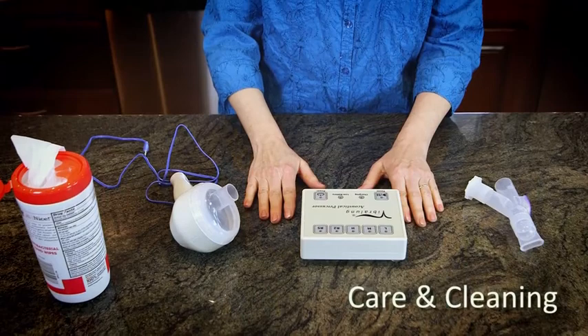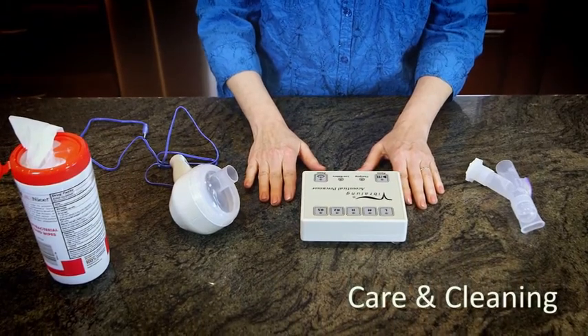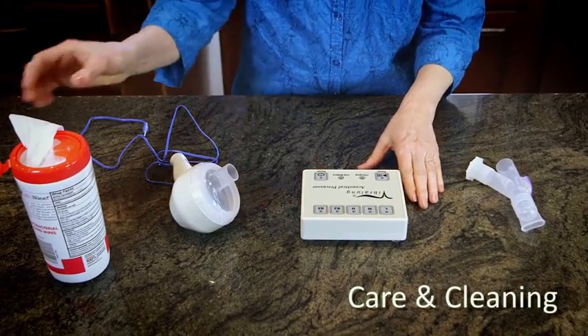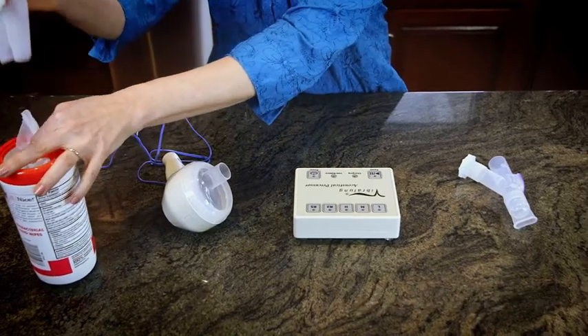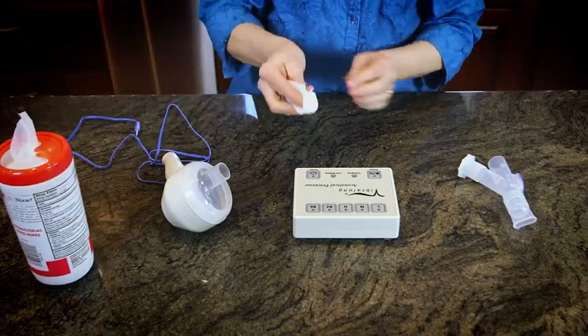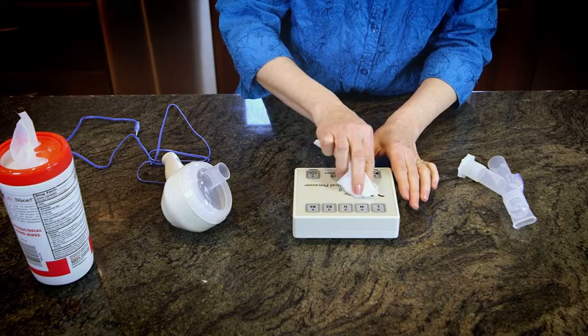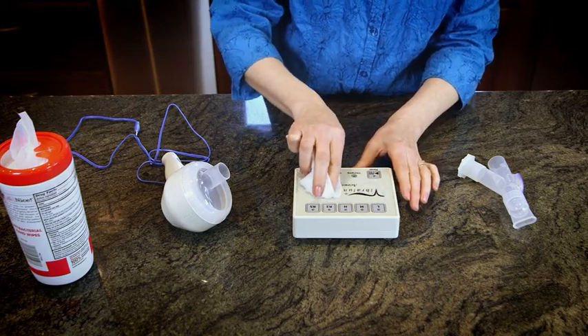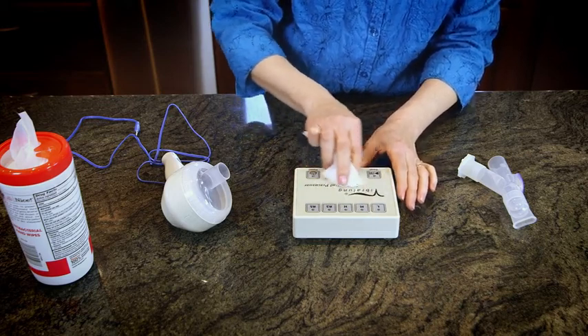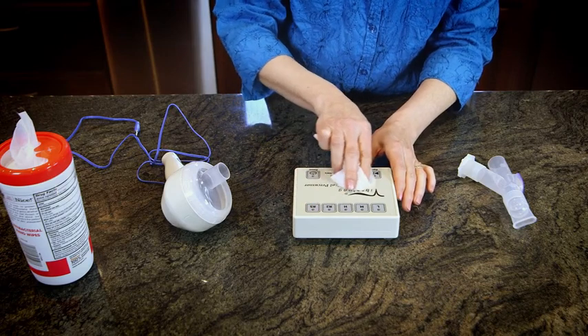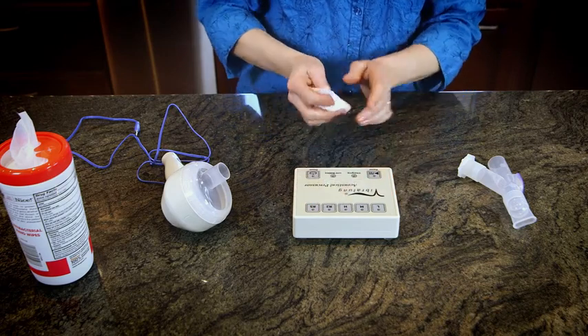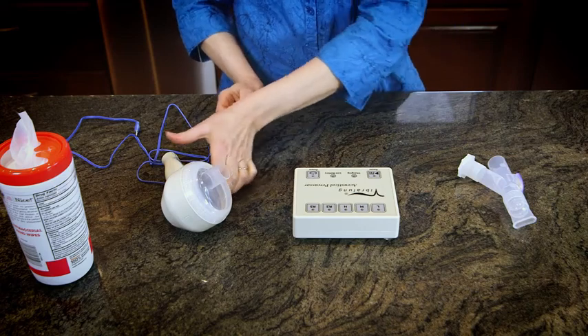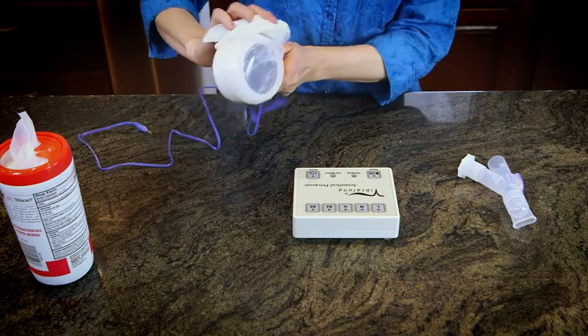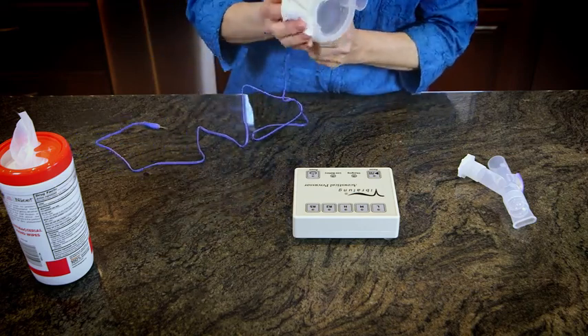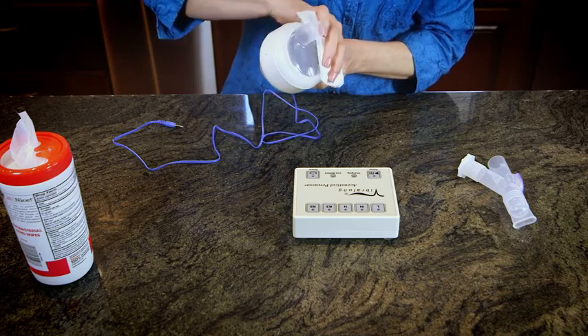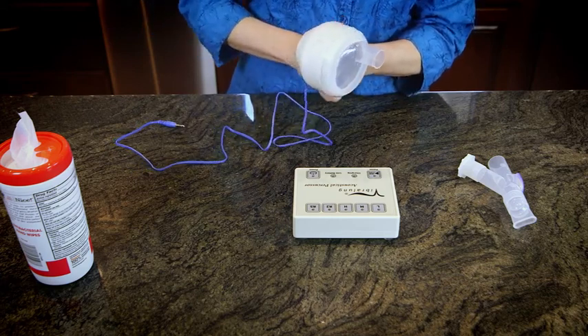The treatment control unit should undergo surface disinfection on a daily basis to minimize surface contamination. Clean all external surfaces with a pre-moistened germicidal wipe product, such as Clorox disinfecting wipes. Ensure that moisture does not enter the case of the treatment control unit at the seams or at the 2 electrical jacks. Wipe down all surfaces of the handheld transducer. Please refer to Vibralung's instructions for use, included in the package, for full instructions on how to appropriately clean all components and proper disposal.